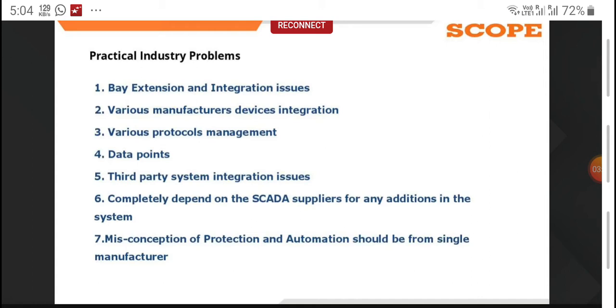In most of the automation systems, when I go to the transmission substations, the executive engineers and superintendent engineers are facing these issues, and they are not getting support from the various vendors. That's why, when they purchase any substation or protection system, they always prefer a single OEM. One OEM can give everything, so they don't need to run behind different vendors for integration problems. They are trying to see how quickly they can get the work done.